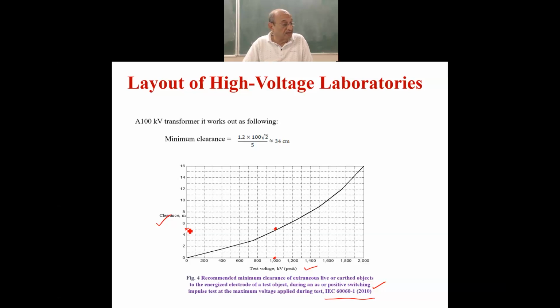So 500 centimeters is recommended. That means for each kV, how many centimeters? For 1000 kV, for each kV, half a centimeter is the requirement, isn't it? For each kV, half a centimeter clearance is required. You can make that a kind of thumb rule. The clearance requirement in air with the other objects is of the order of half a centimeter per kV, considering the peak value of the AC power frequency. In other cases, it is the peak value. So this is 0.5 centimeter per kV peak.